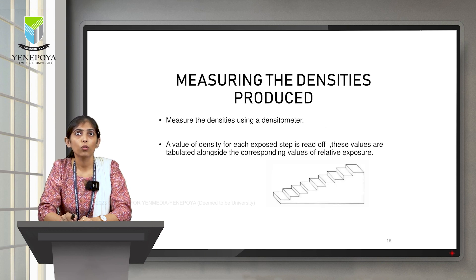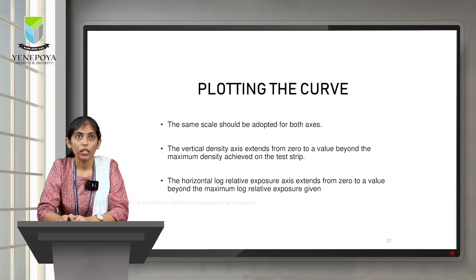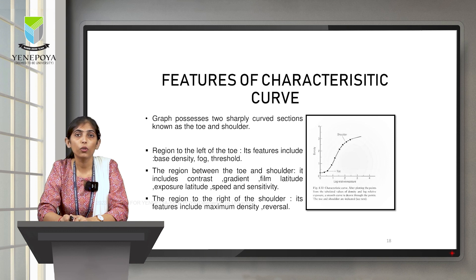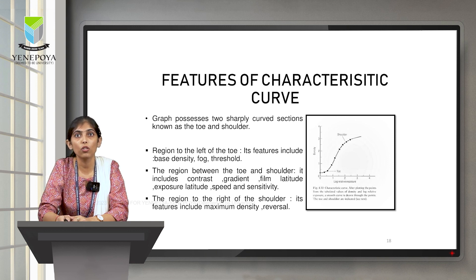The densities produced are measured using a densitometer, which is a device that helps in measuring the densities. The final step is plotting the curve, with density on the y-axis and log relative exposure on the x-axis. This curve has three parts: the region to the left of the toe, which gives base density, fog, and threshold; the region between the toe and the shoulder, which tells about contrast, gradient, film latitude, exposure latitude, speed and sensitivity; and the region to the right of the shoulder, which tells about maximum density and reversal.